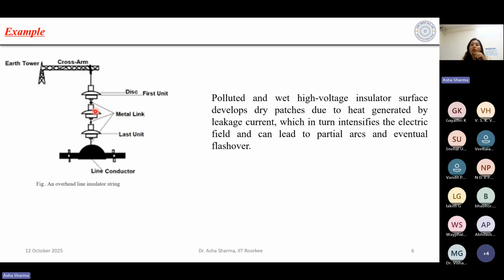This is not something that happens only in one certain type or only here. This is called dry band formation. Because of dust, dirt, and foggy weather, it may happen across the insulator string, and there will be several flashovers, ultimately leading to puncturing of the insulator.